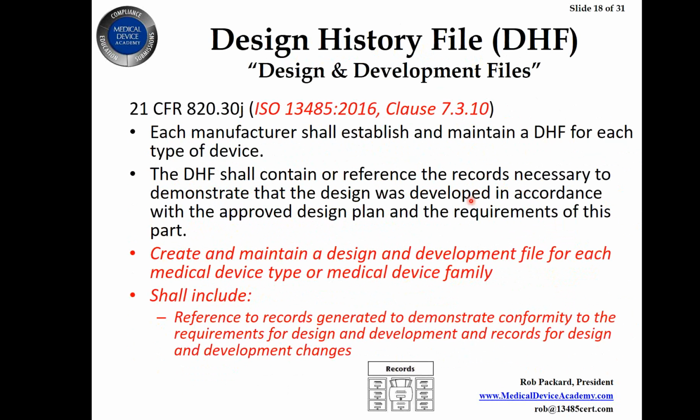So when you do a design history file, if you have a design history file that applies to a family of products, it's okay to have a design history file that's a family if it's minor changes in like sizes.